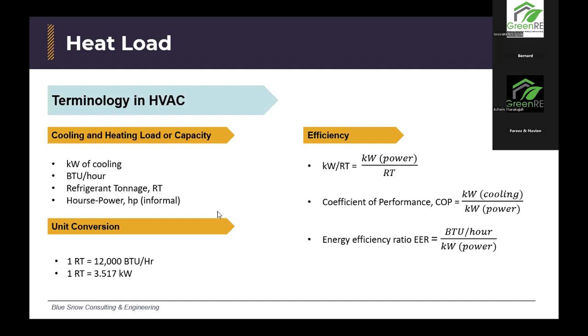So for unit conversion, since I mentioned that RT, or refrigerant tonnage, is the most used unit: one RT is equivalent to 12,000 BTU per hour, and one RT is also equivalent to 3.517 kilowatt. If we mention kilowatt, there are two types of kilowatt. The first kilowatt is for electricity power consumption, and the second kilowatt is the one I mentioned here, which is for cooling. So these are two different things, and you need to differentiate them. In the efficiency calculation of the HVAC system, the first one we use is kilowatt over RT, which is the kilowatt of electricity divided by the RT, the refrigerant ton or cooling capacity.